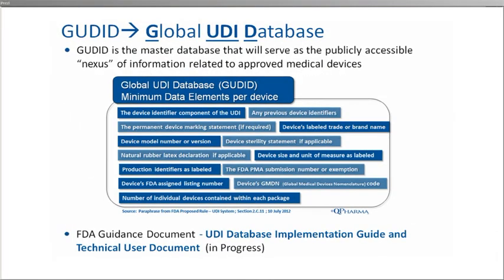So, Tom, where does the UDI go when it's submitted? As you might have guessed, the destination for all UDI data is another acronym. It is the GUDID, or GOODID, the Global UDI Database. This will be the publicly searchable master database of all medical devices approved for sale in the United States. Manufacturers will be required to submit data elements for their product to populate the GUDID. This graphic shows 13 minimum data elements per device the FDA is expected to require for submission.